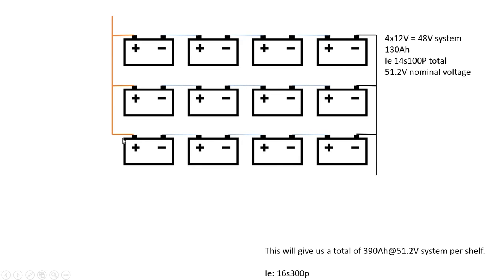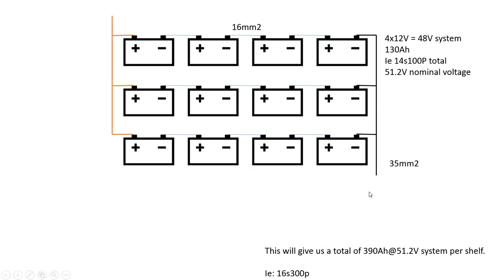The big importance here is how you do it and make sure that the lengths are equal between each set. As you can see I draw power from one cross end to the other to make sure that we have an even draw. The cables on the negative side and positive side ends are 35 square millimeters meanwhile the cables or wires in between the batteries are 16 square millimeters.